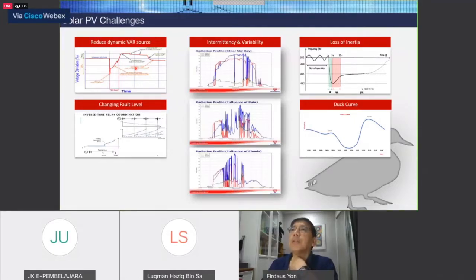Changing fault level, I've mentioned two things. Our major switching equipment, the primary equipment, the circuit breakers and bus, was designed for one-way power flow, and the fault levels were calculated based on that, on the impedances. Now there's bi-directional power flow.